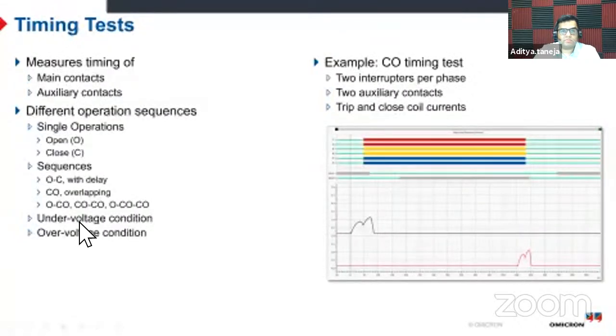And also these tests are done in under voltage and over voltage conditions to make sure that, at the boundary conditions, the breaker should work satisfactorily in extreme conditions.